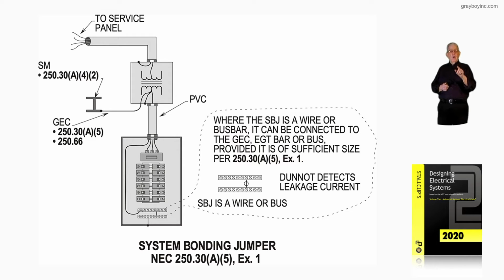Then notice a little donut is put between that strap that you would have there that is connected to the bar that is bonded and grounded to the enclosure. And then we could have, say, equipment grounds routed back to the grounded bar that's bonded to the can. And we could put a little donut there and monitor leakage current that may be coming back over the equipment grounding conductors and know if we have objectionable current flowing.